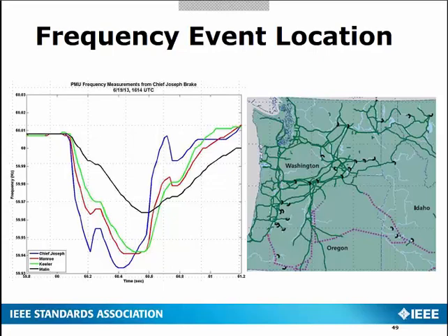From this, you can see that at these precise locations, go ahead and click through these locations. The blue location is Chief Joseph, where the load brake is located. Red is in the Seattle area, green is in the Portland area, and black is in the Southern Oregon area at the end of our system. You can see the precise effect of the system being slowed down by that single load brake using phasor measurement units.